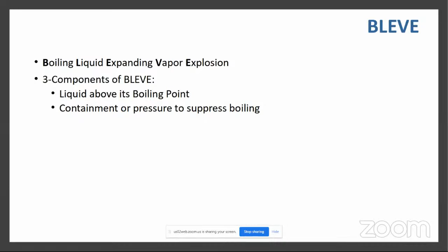First, we'll start with the fundamentals of BLEVE. BLEVE is an acronym for Boiling Liquid Expanding Vapor Explosion. Just as a fire triangle needs a source of ignition, oxygen, and fuel, a BLEVE needs three fundamental conditions to occur: the liquid or material must be above its boiling point, it must be in a closed containment under pressurized atmosphere to suppress boiling, and there must be a sudden loss of containment. If all three conditions are met, the possible outcome is a BLEVE.